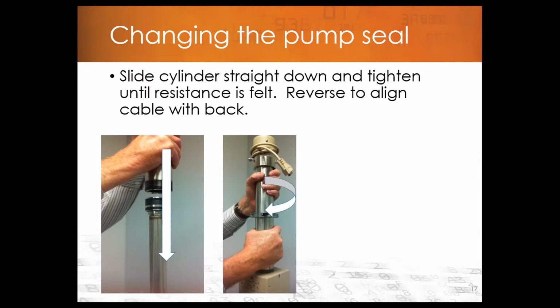Because if the cylinder is scratched or has a score mark that's deep enough, if you put the cylinder back on and pressurize the pump, it's going to leak. Because those scratches are going to prevent the piston seal from sealing against the cylinder wall, and the material or liquid that you're pumping is going to get past the seal, and you'll still have leakage. So you want to make sure that your cylinder is in good condition, and as I indicated, it should be a mirror finish. If there's residue on the cylinder, then before you put the cylinder on, I would rinse it out with something like water, or you can use isopropyl alcohol, methanol, something to rinse the cylinder out if there's any residue that's left behind from whatever you're pumping.